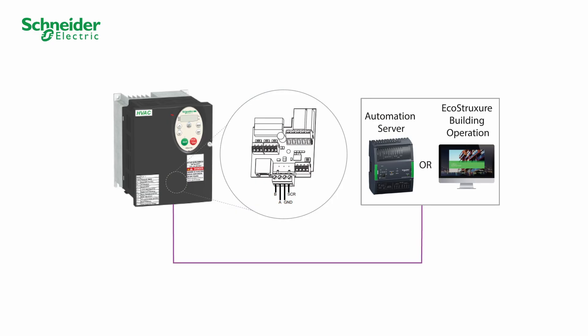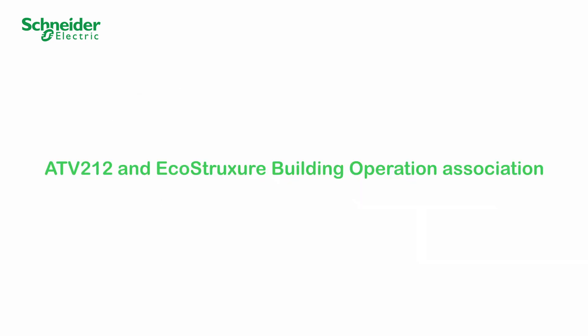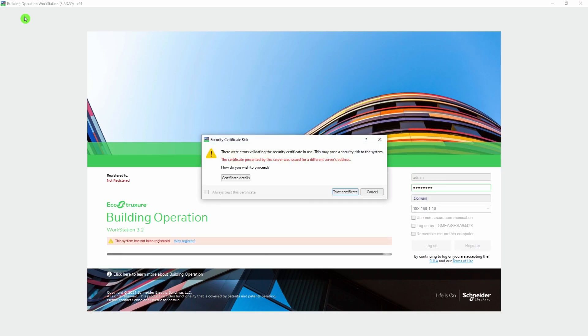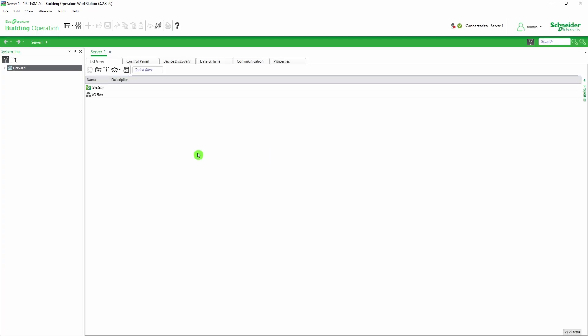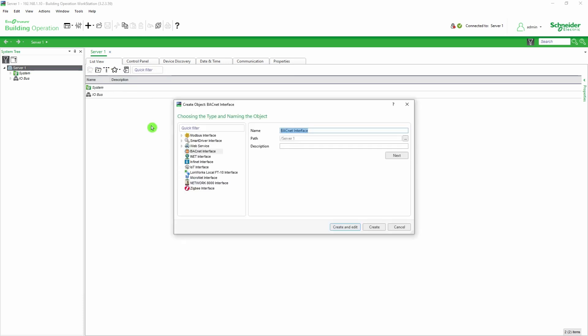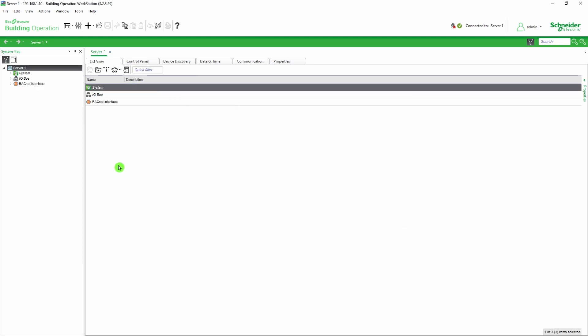To connect the ATV212 to the device, refer to the ATV212 BACnet manual. For ATV212 and EcoStruxure Building Operation association, log on to the workstation and open the engineering workspace. Create a BACnet interface and MSTP network, then add the MSTP network to your BACnet interface.